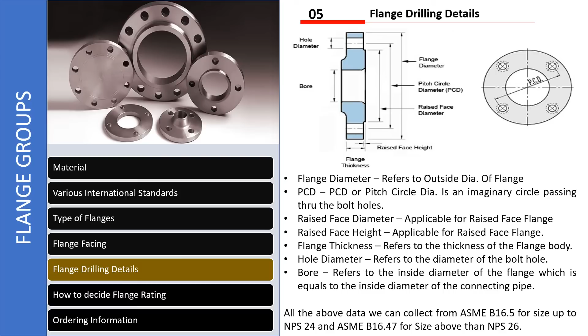Flange rating. This is a really important term when we talk about flanges. Let us try to understand what it is and how we refer to it. First of all, it is the maximum pressure that a flange can withstand at a particular temperature. So it is a pressure and temperature bearing capacity. It is a pressure and temperature combination, and for that combination there is a maximum pressure which a flange can bear. That is the basic PT rating definition, you can say.